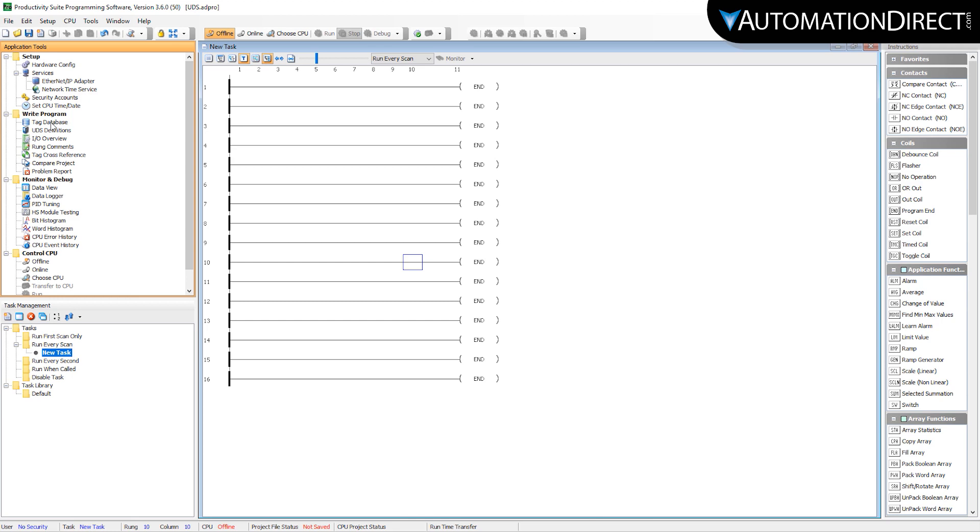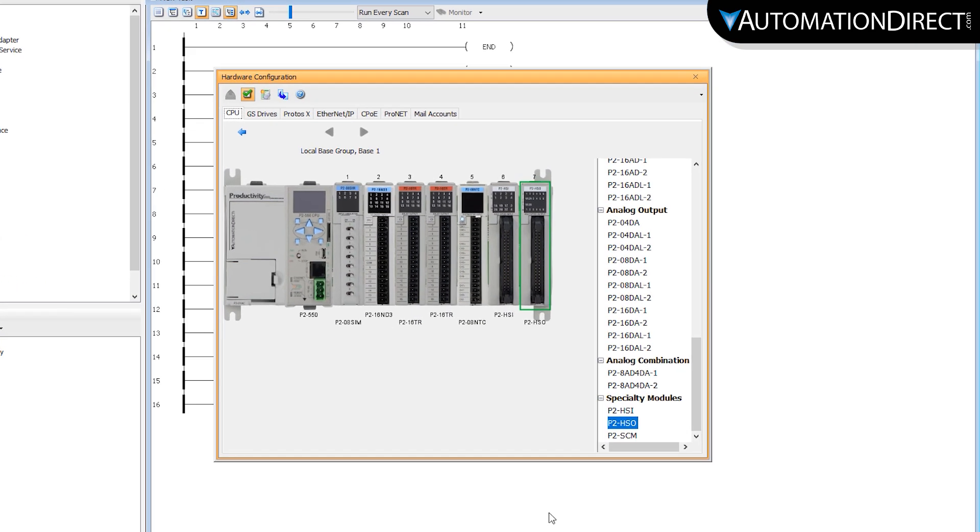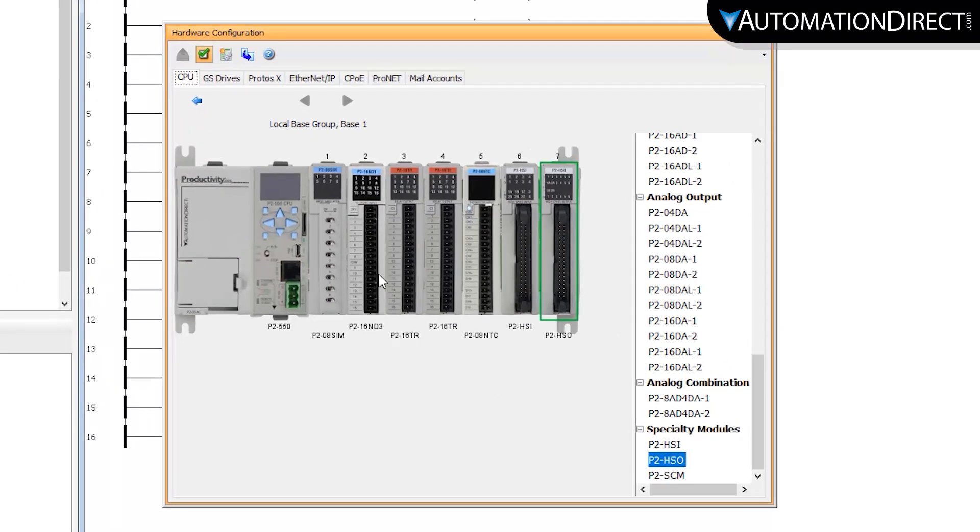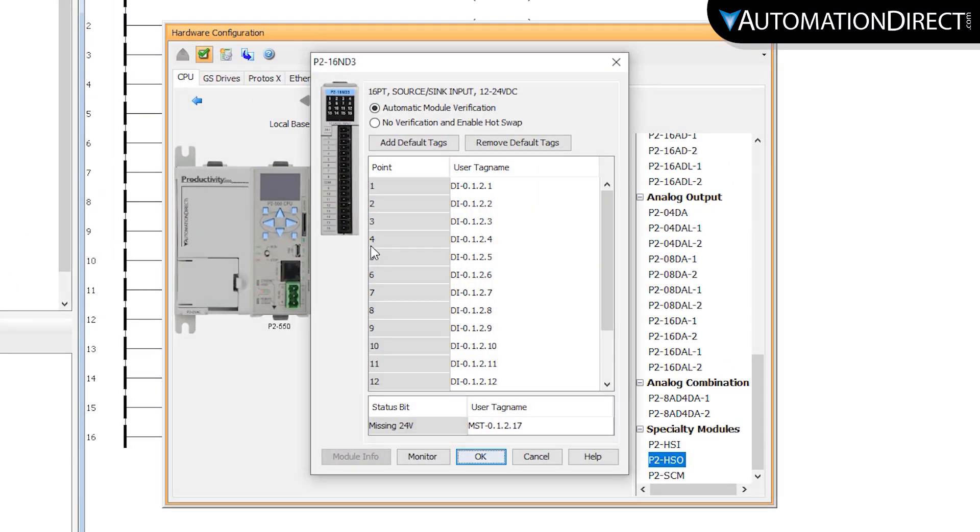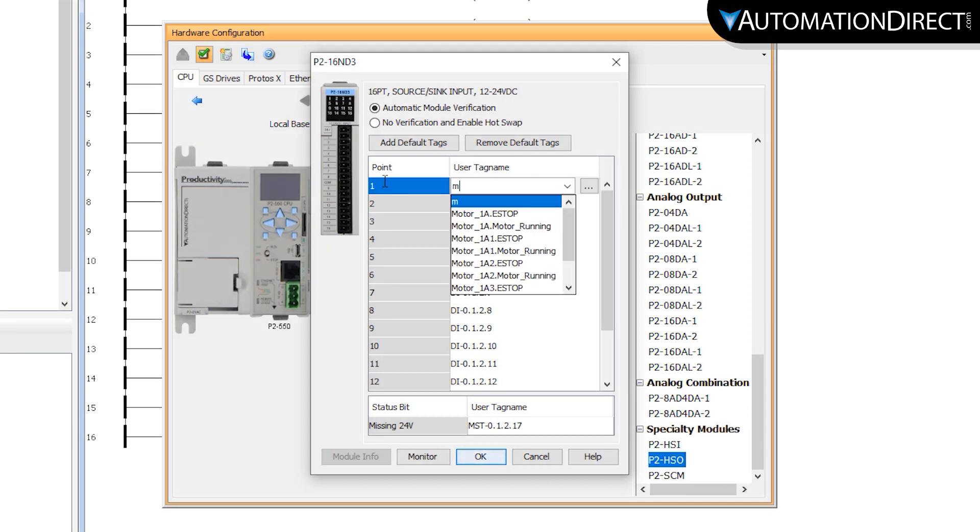This is done easily by going into the hardware configuration, selecting the input or output module that the physical input or output is wired, and applying the tag name created from our UDT.